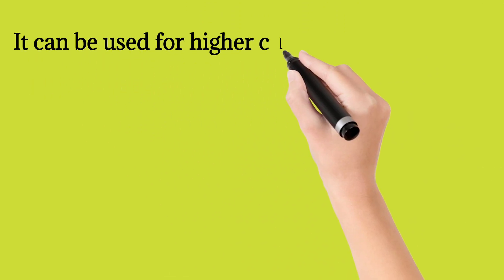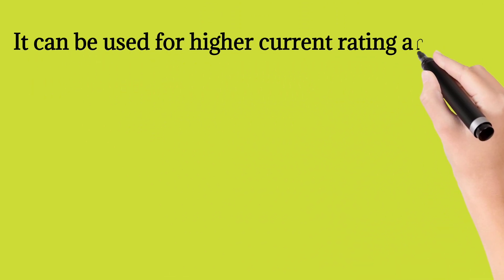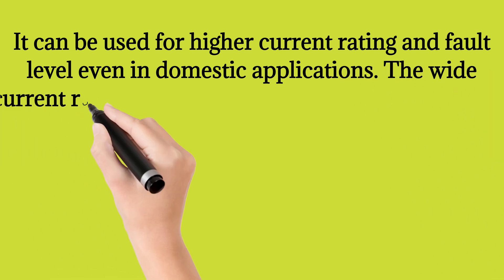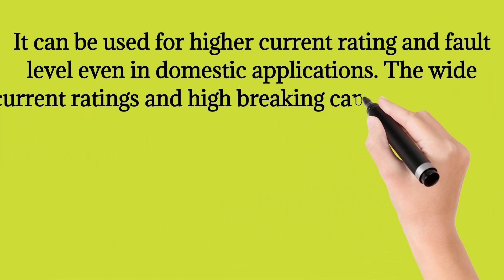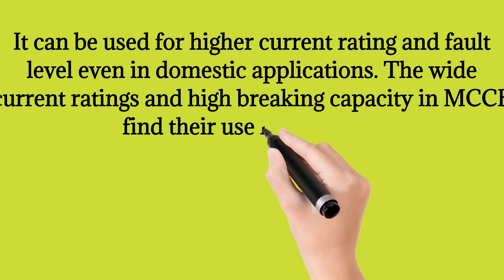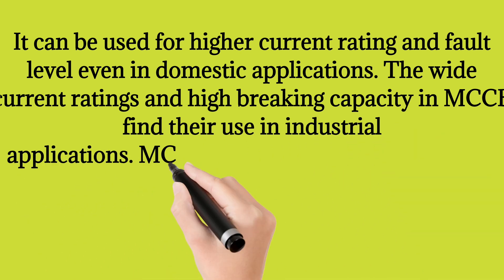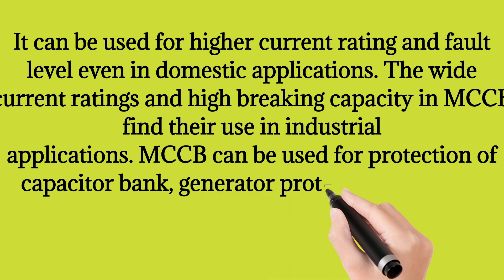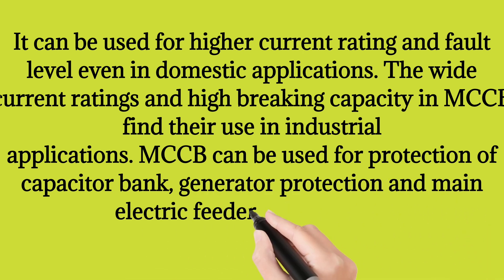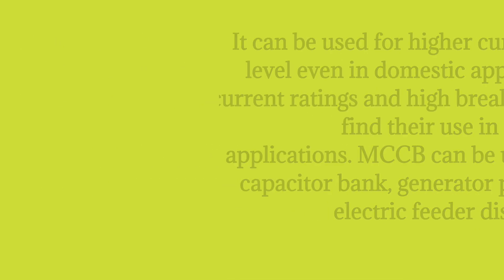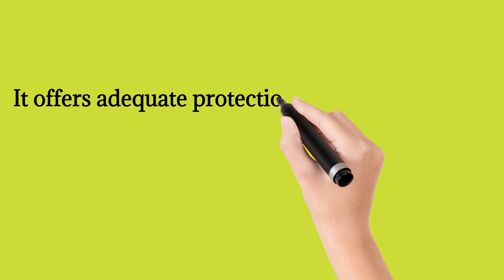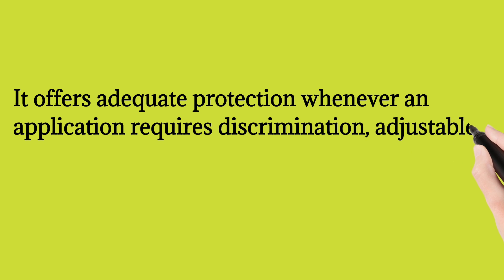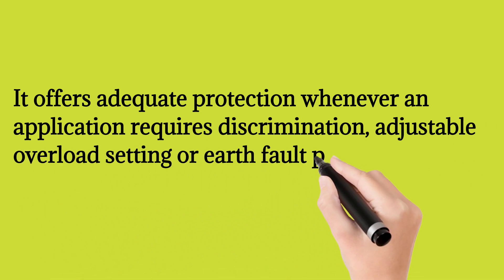MCCB can be used for higher current ratings and fault levels even in domestic applications. The wide current ratings and high breaking capacity in MCCB find their use in industrial applications. MCCB can be used for protection of capacitor banks, generator protection, and main electric feeder distribution. It offers adequate protection whenever an application requires discrimination, adjustable overload setting, or earth fault protection.